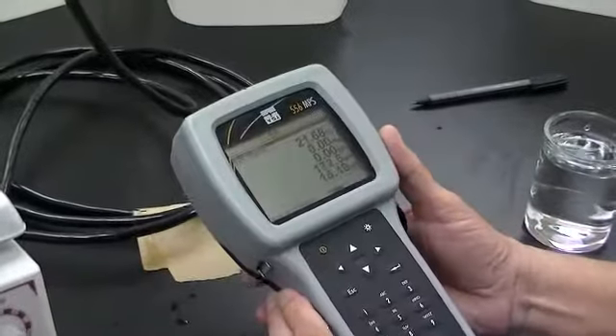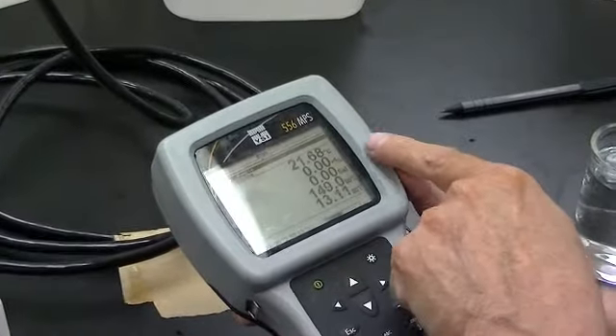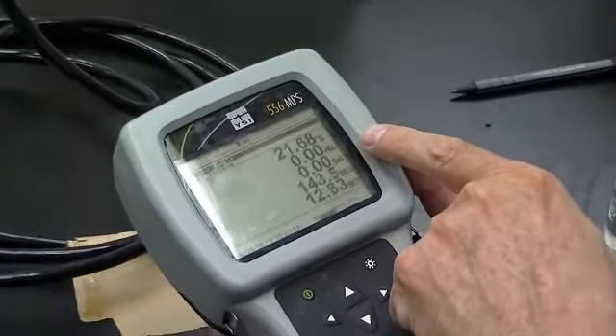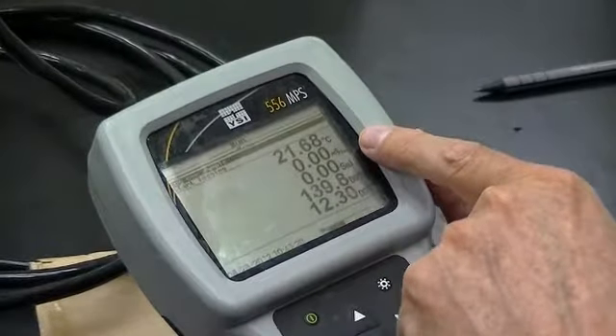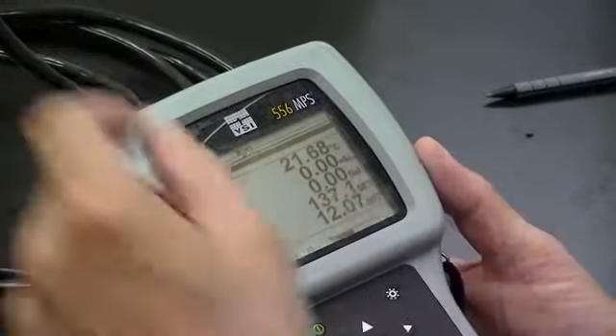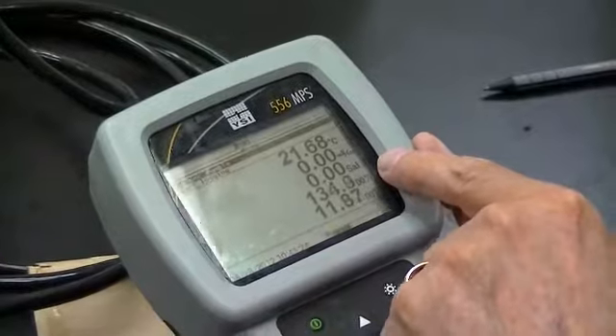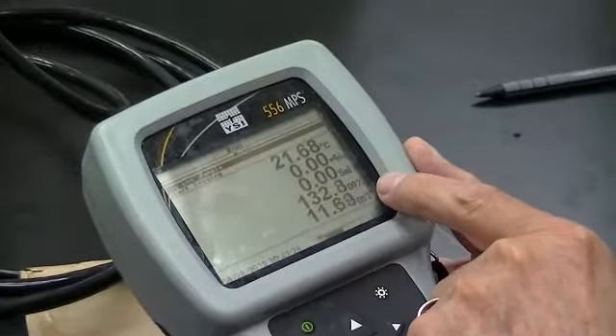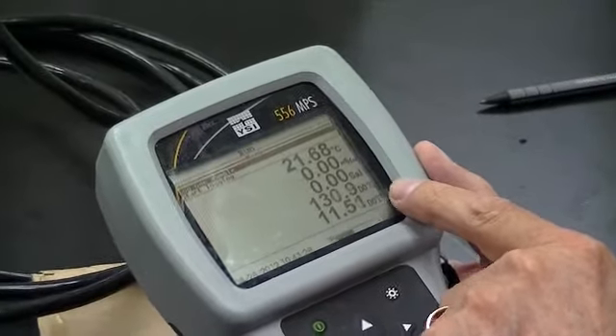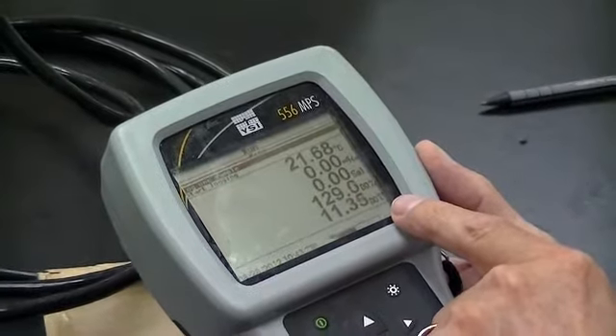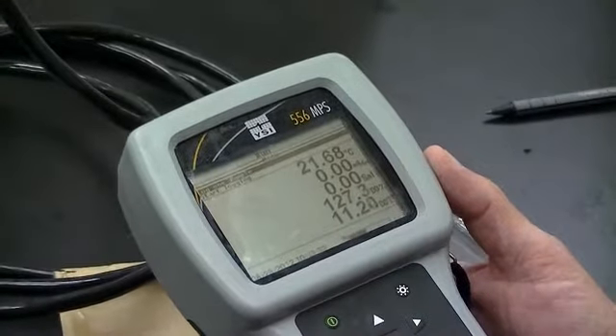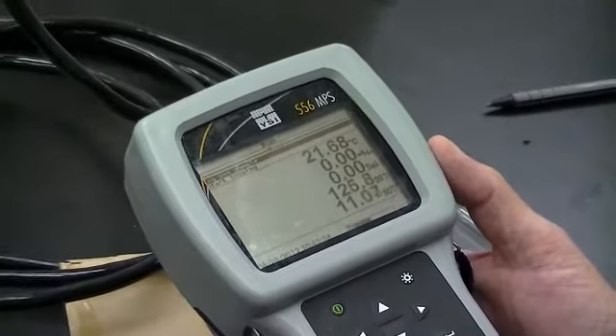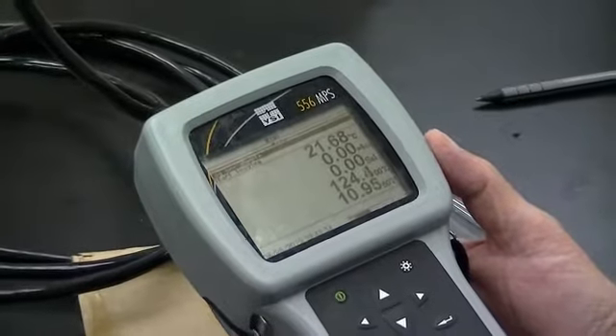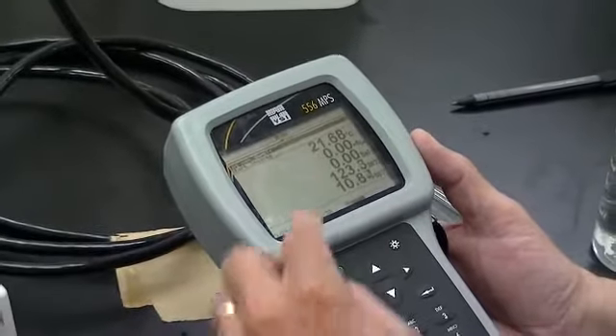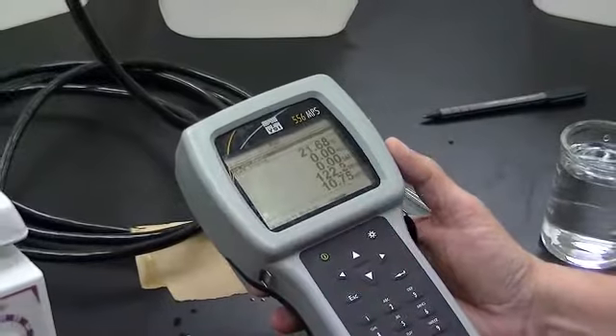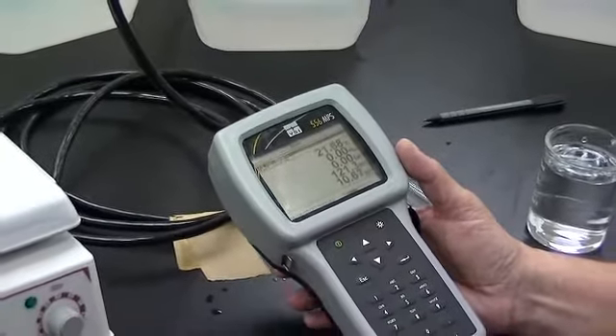And just quickly, the display has at the top temperature, then conductivity, which now reads 0 because the probe is in air, salinity, which now reads 0, and then dissolved oxygen percent saturation and dissolved oxygen concentration. That's coming down. The numbers are changing rapidly now because I just turned the instrument on. But we'll be interested in the top 3 numbers, not the oxygen. That comes in another lab.